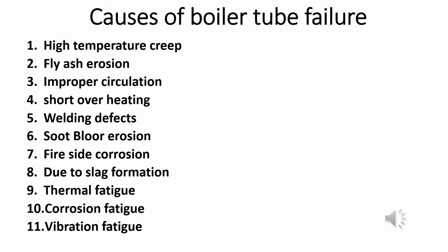Number 11 is the vibration fatigue. Vibration fatigue is the most important thing. If your loading and unloading of the boiler is not proper, meaning that you are suddenly loading the boiler and suddenly unloading the boiler, then there will be high vibration in the boiler. And if your air fuel ratio is not proper and your governing system is not good, then there will be a lot of chances of the boiler vibrating. Due to vibration, stresses generate in the tubes and joints of the tubes, which ultimately results in the failure of the boiler tube.